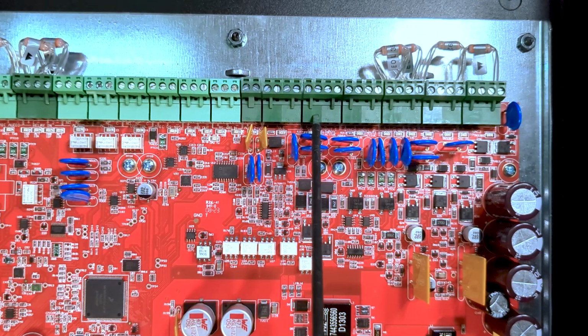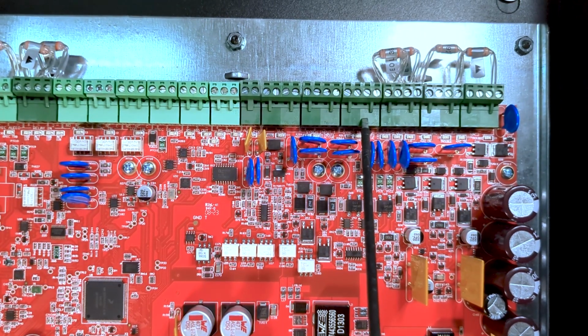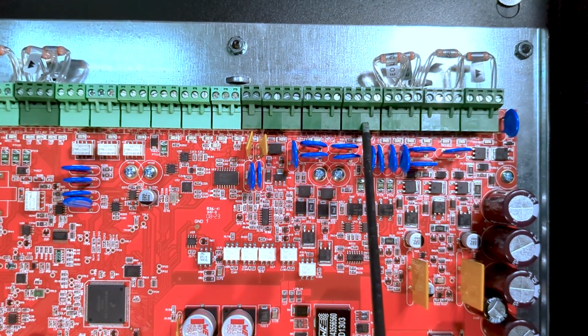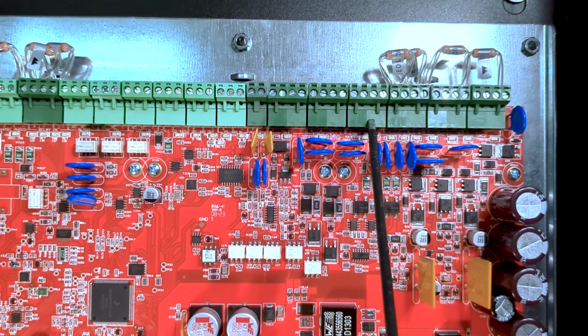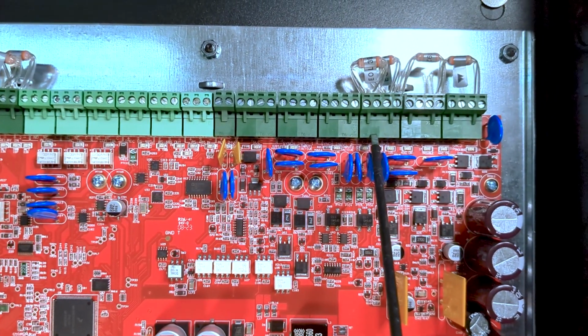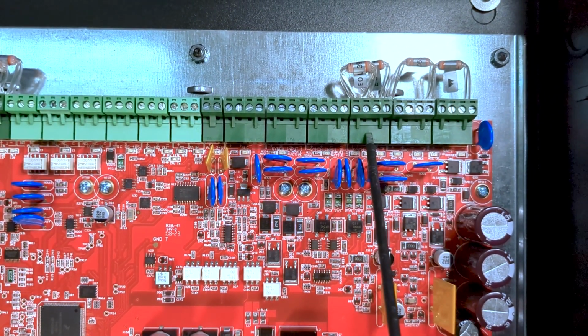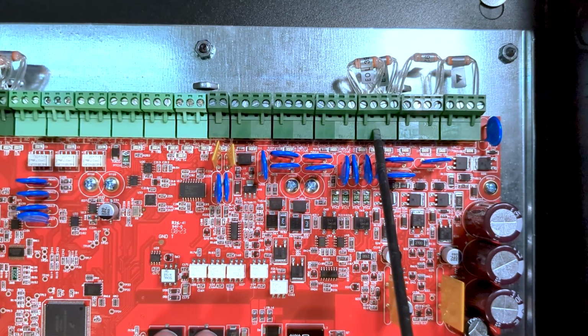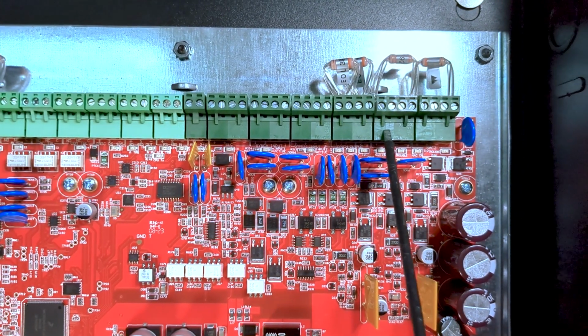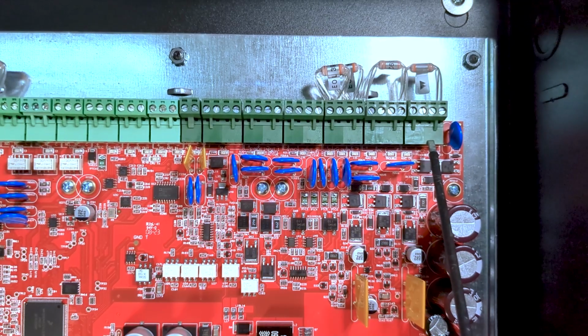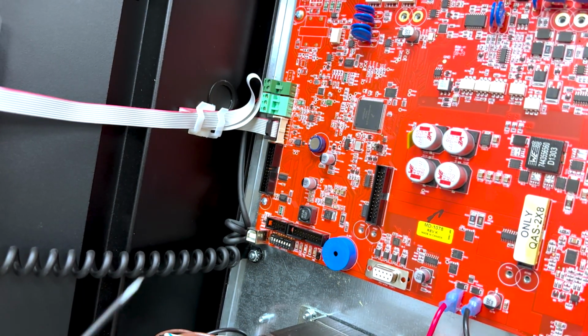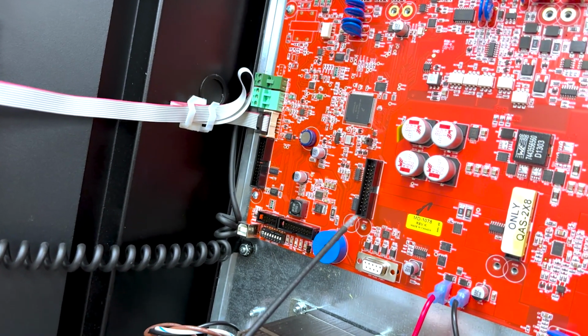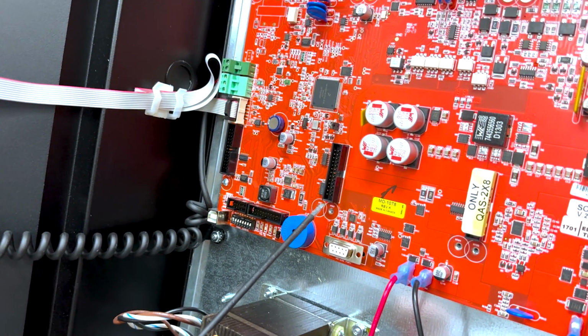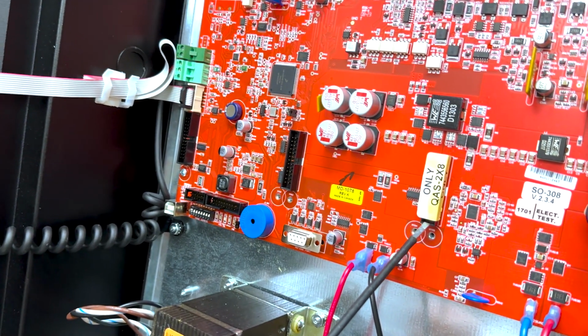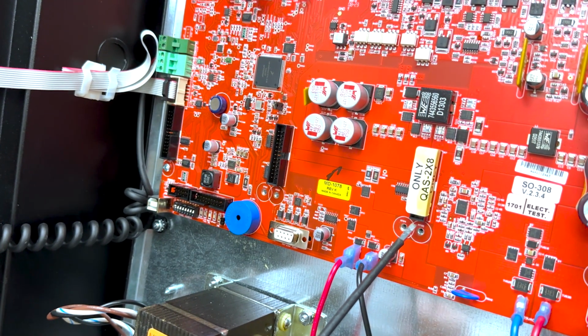To the right, we have two sync inputs that pass synchronization from NAC circuits, which can also be used to activate zones. The sync output connects to subsequent booster panels to pass along the synchronization. Next, we have two regulated 2.5 amp NAC circuits to drive horns and strobes. In the middle of the MD1078, we have three connection ports. P5 and P6 are reserved for amplifiers 1 and 2, and P7 is reserved for the QAS 2x8 splitter card.